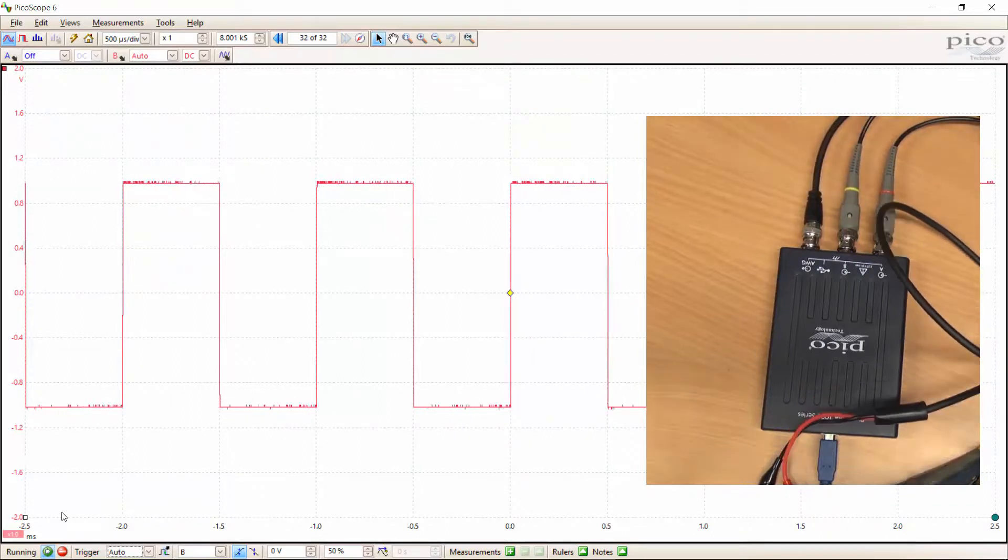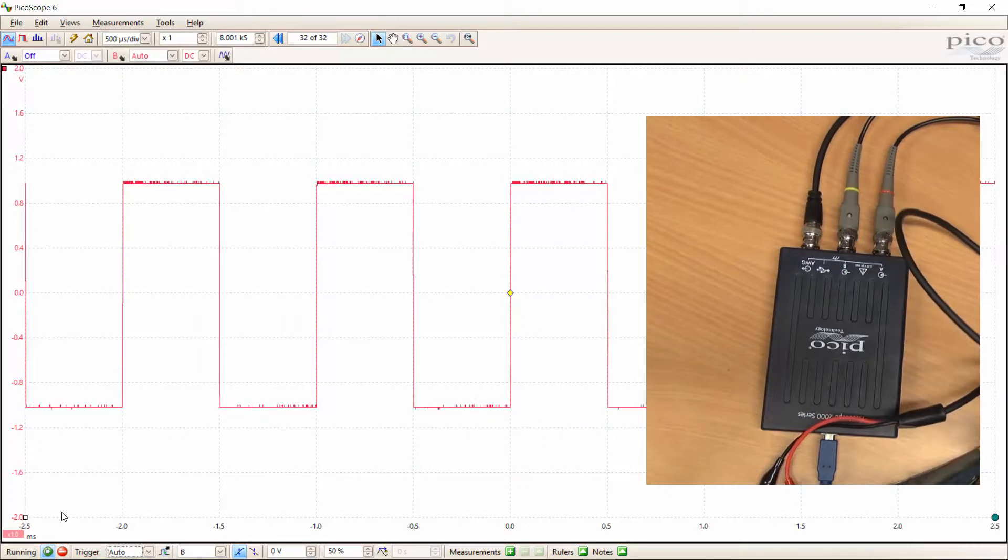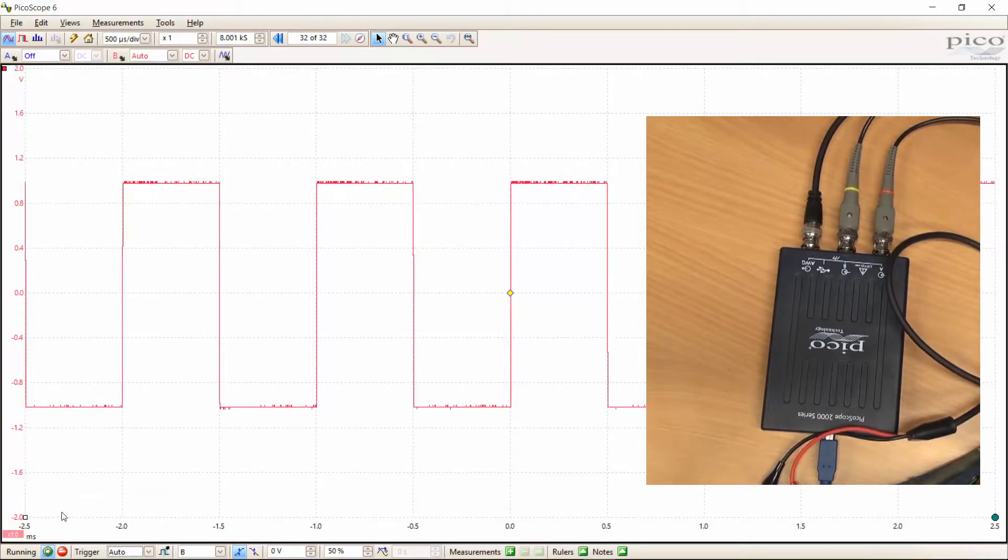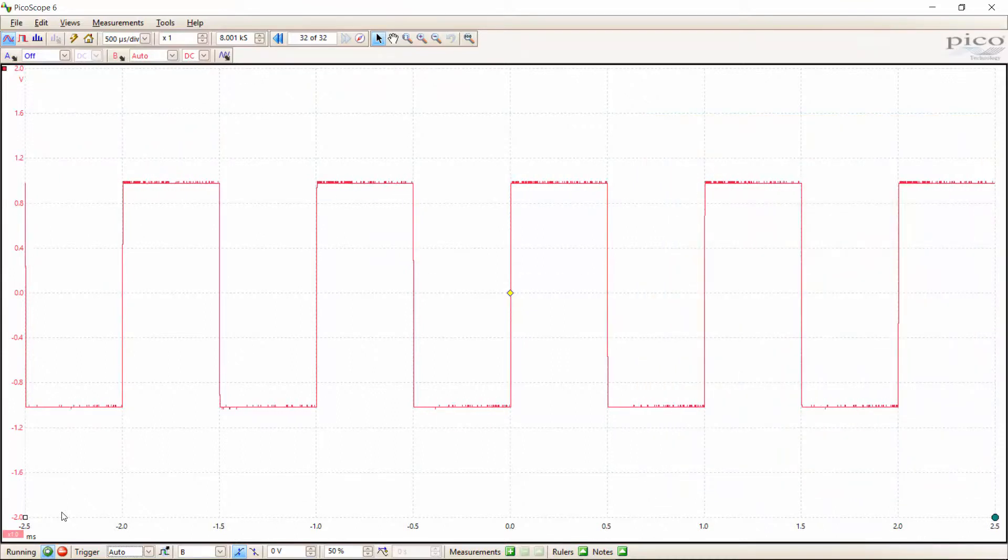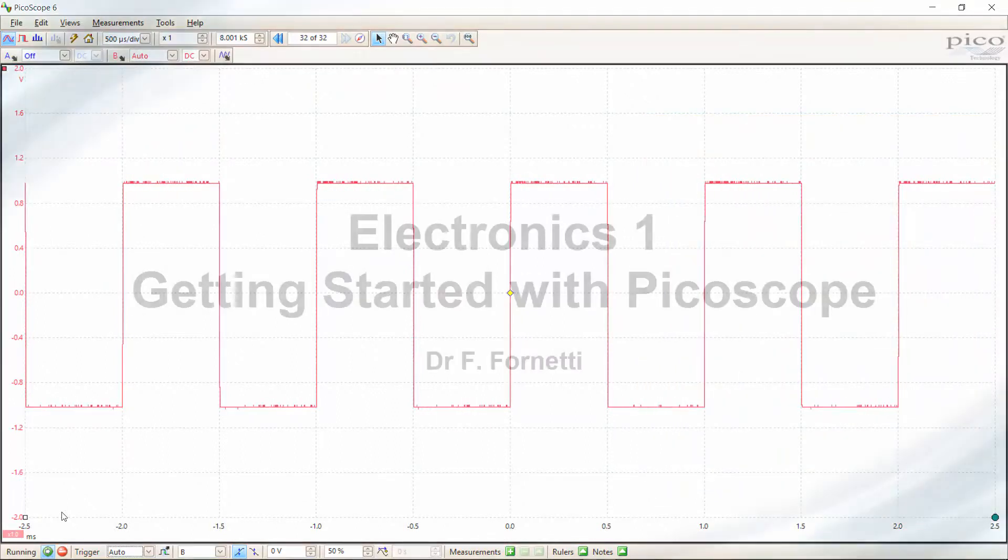We can simply work our magic until we get a flat top and a flat bottom. So now we've got our two probes calibrated correctly, and we can proceed to carry out any other measurements that we wish to carry out with the oscilloscope.